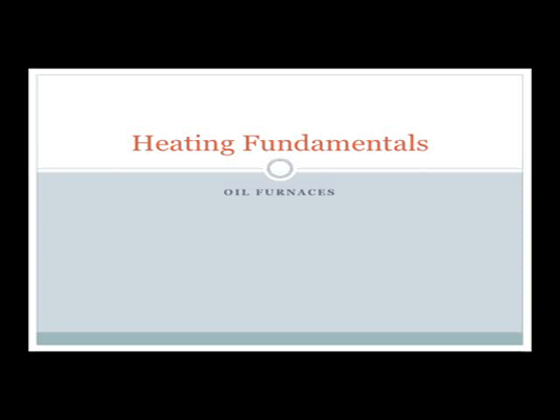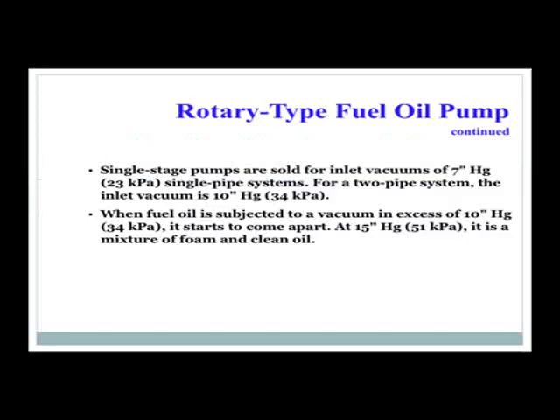This is the second part in the oil furnaces lecture for heating fundamentals. We left off at the oil pump, and that's where we're going to continue. The rotary-type fuel oil pump we had talked about in the first lesson is a single-stage pump. It handles inlet vacuums of 7 inches mercury for single pipe systems. For a 2-pipe system, the inlet vacuum is 10 inches of mercury.